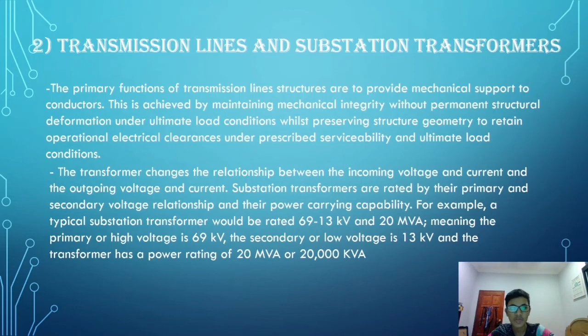The transformer changes the relationship between the incoming voltage and current and the outgoing voltage and current. Substation transformers are rated by their primary and secondary voltage relationship and their power carrying capability. For example, a typical substation transformer would be rated 69, 13 kV and 20 MVA, meaning the primary or high voltage is 69 kV, the secondary or low voltage is 13 kV, and the transformer has a power rating of 20 MVA or 20,000 kVA.